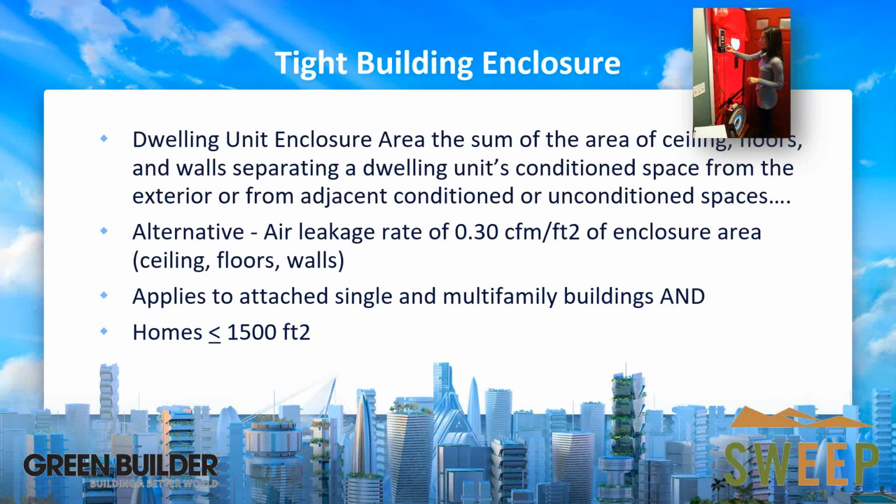And so next energy code, and we've been seeing it happen at the state and local level where updates to the code or amendments to the code have occurred where they're including the ability to look at dwellings, multiple dwellings, attached dwellings. And so that becomes a challenge with the ACH, the air change per hour. Well, the test is the same, but to get to the ACH, you'd have to do guarded testing, you'd have to know what the pressure is on both sides of the buildings to do an accurate ACH.